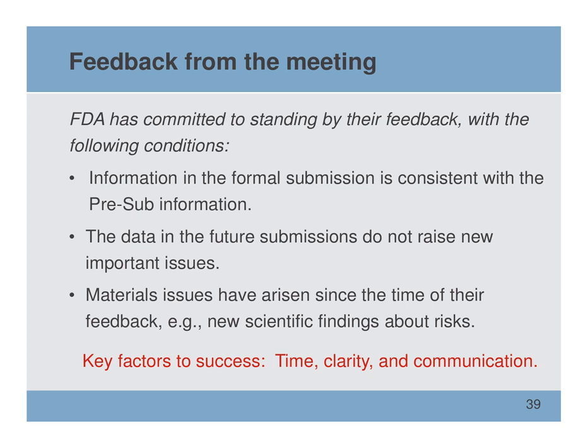Remember the Goldilocks principle for device description, right? So if you tell them, well, we changed something, you can say, well, it was only a very small thing, and it doesn't really impact your previous decisions with FDA. But then again, if something has happened, then call them up, let them know that something's changed, and get their feedback on it, and get their agreement, hopefully, that, oh, yeah, all you have to do is to redo test 1, 2, and 4. You don't have to redo test 3. And then keep track of the science in your field. If FDA is going to come back and say, we learned something new, well, hopefully you know that, and when they tell you that, you can say, hey, I understand you may take it that way, but here's the way we understand it.